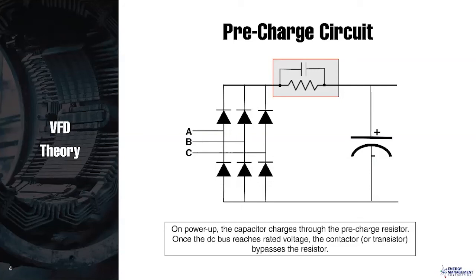Now, once the voltage on the capacitor is at your rated voltage, then the contactor will close. It bypasses that resistor, and so that resistor is in there for a fraction of a second, and then it's gone. So we're going to take it out of the circuit because it effectively isn't there once that contactor closes. As you can probably see, if you energize the drive and then you measure the DC bus and there's no voltage on the DC bus, there's a very good possibility that that resistor is broken. Let's go to the next slide.